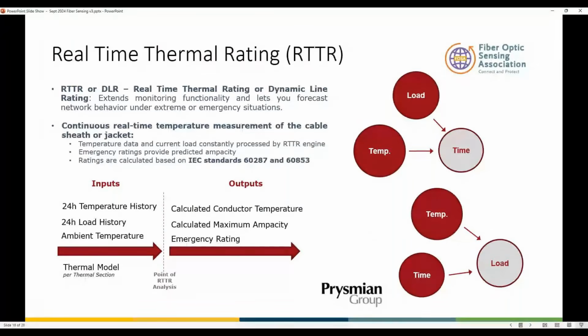The key point here is that distributed fiber optic sensing, or distributed temperature sensing, does not by itself provide the real-time thermal rating, but it's one of the key inputs. The ability to accurately measure temperature at small spatial resolution across the entire length of the asset is an enabler to real-time thermal rating, or dynamic line rating.